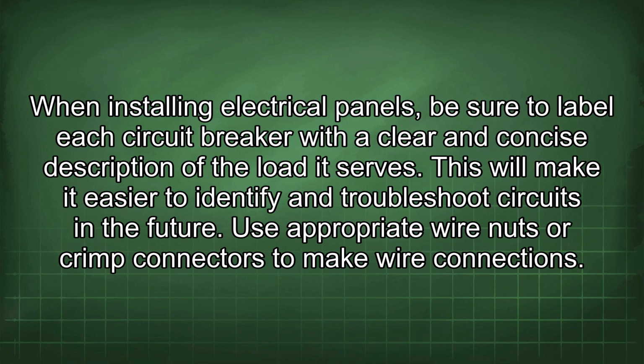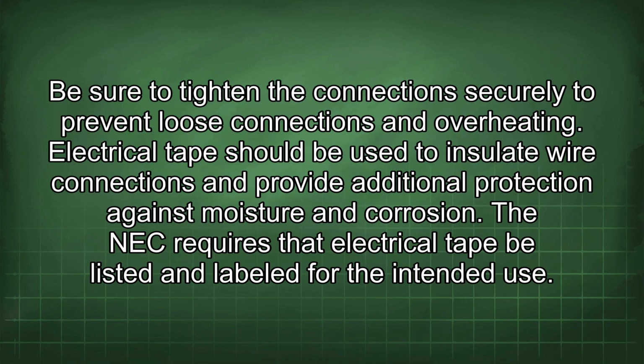When installing electrical panels, be sure to label each circuit breaker with a clear and concise description of the load it serves. This will make it easier to identify and troubleshoot circuits in the future. Use appropriate wire nuts or crimp connectors to make wire connections. Be sure to tighten the connections securely to prevent loose connections and overheating. Electrical tape should be used to insulate wire connections and provide additional protection against moisture and corrosion. The NEC requires that electrical tape be listed and labeled for the intended use.